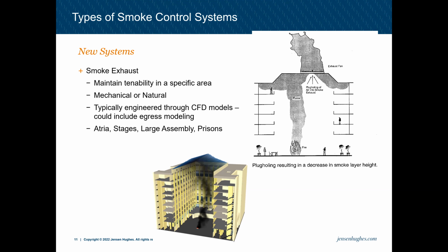And the main idea, if we see in the picture in the top right corner, is that usually in an atrium, we have a larger fire load of items, such as a Christmas tree. We have a bunch of furniture down below, maybe a couple of kiosks, and these tend to have a much larger fire load, and we can't control these fires by sprinklers. And so if it's open up to the higher floor, as shown in that top right picture, somebody can be exposed to those toxic gases and those dangerous temperatures when they wouldn't normally be exposed to that during a regular fire if we were being controlled by sprinklers on just a regular floor. So that's why atriums are usually included in this.